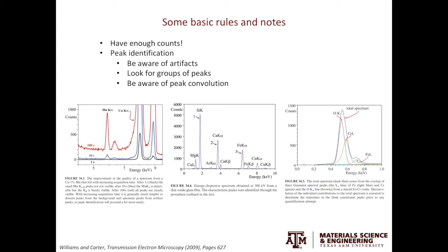With X-ray energy less than 1 keV, you have the K X-rays from light elements, such as carbon and oxygen, and L X-rays from the transition metals. In the example shown on the right, the chromium peak is convoluted by the oxygen peak.